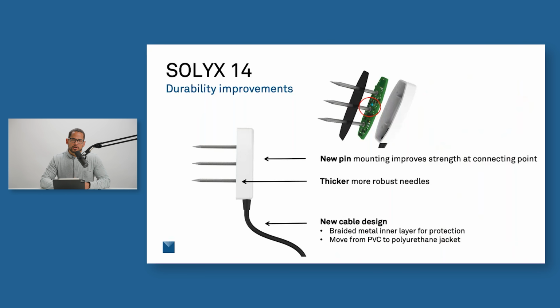But also, one of the key failure points that we see in soil moisture sensors is the cable. And so we also worked on a new cable design with a braided metal inner layer to help protect the cable from potential abrasion and damage from rodents. And we also moved from a PVC to a polyurethane jacket that allowed us to manipulate the cable a little bit better. Now, having said that, cable protection with conduit is still critical, especially for long-term monitoring applications. No cable is impervious to rodents. And so we want to make sure that you're still protecting your cable, but we're continuing to try and make improvements in the ability of the cable to survive some of those things, so we see less failure of our soil moisture measurements over time.